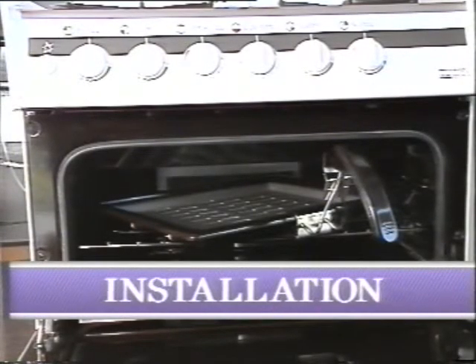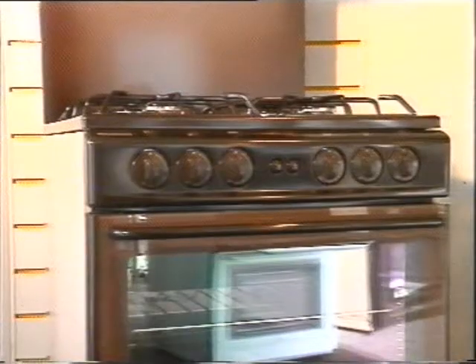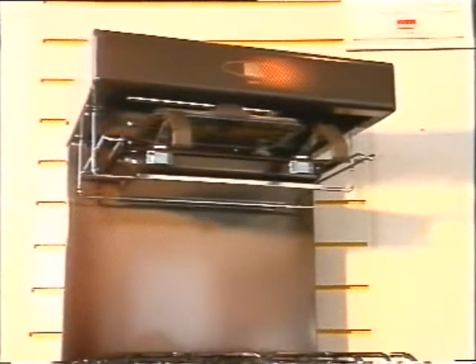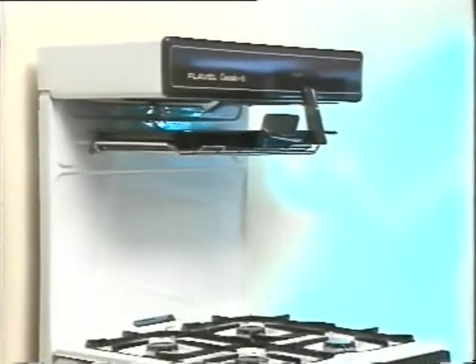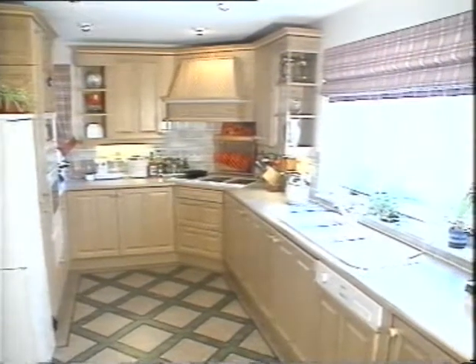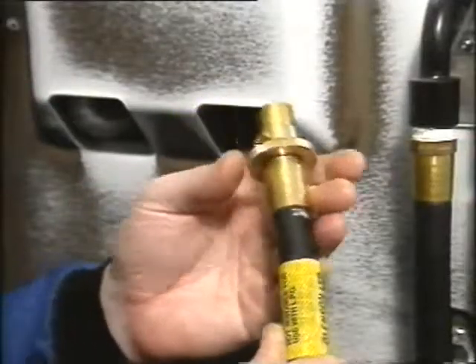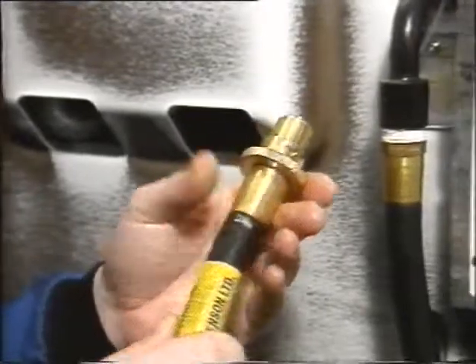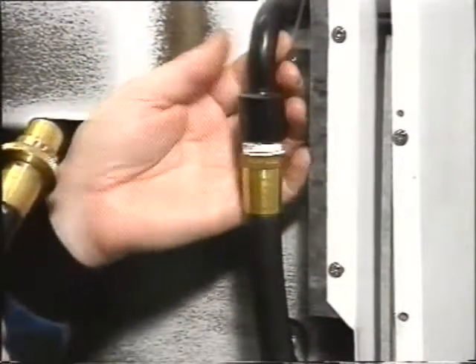Before installing a cooker, check the relevant BS regulations and, of course, the manufacturer's instructions. You'll find details of where you can and can't install it. Cookers are not allowed in bathrooms, shower rooms, or bed sits smaller than 20 cubic meters. They shouldn't be installed where they might be affected by excessive drafts or where they may cause an obstruction. BS regulations give very clear guidelines on points like clearance, the condition and strength of floors and work surfaces, and the presence of combustible materials. They also cover ventilation needs for rooms of varying sizes and characteristics. The types of connections used, gas and electric, are important both for natural gas and liquefied petroleum gas, LPG. Once again, the BS regulations are detailed and you must consult them every time.